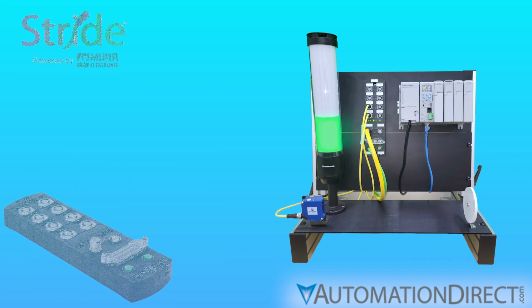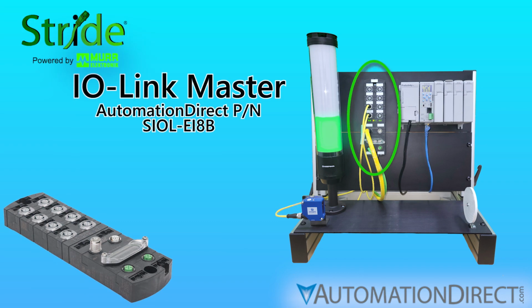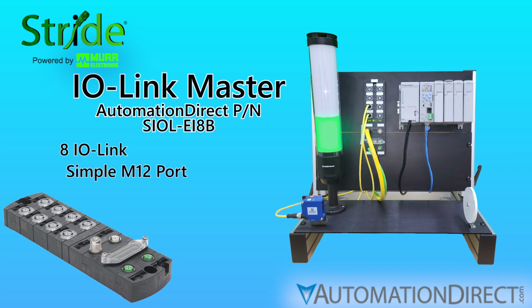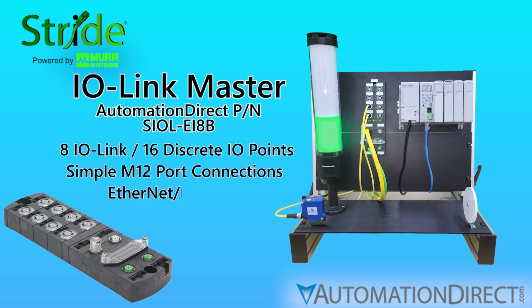The Stride Basic IO-Link master allows a PLC to connect with up to 8 IO-Link-capable field devices with no complicated field wiring. Simply plug the devices into the master's 5-pin M12 ports. If not connecting to an IO-Link device, each of the M12 ports can handle 2 simple discrete I/O points. On the other side, the master is in dialogue with the PLC over an EtherNet/IP connection, relaying device status, PLC commands, error reports, and system data back and forth between the PLC and each connected field device.